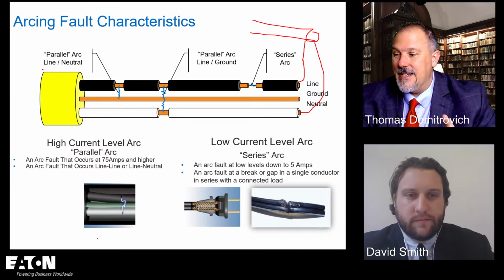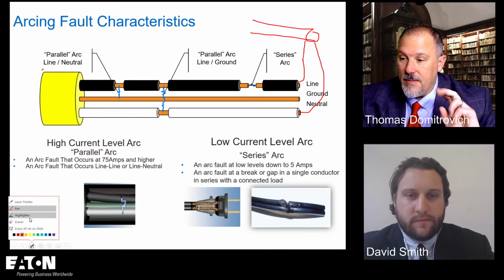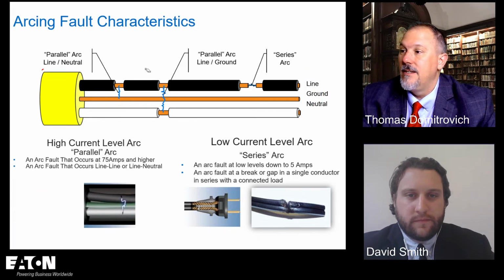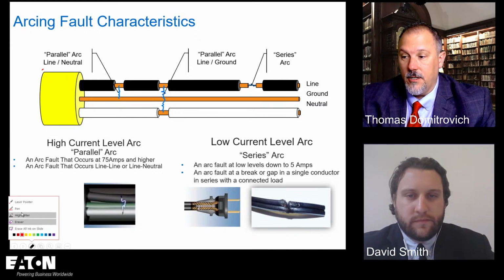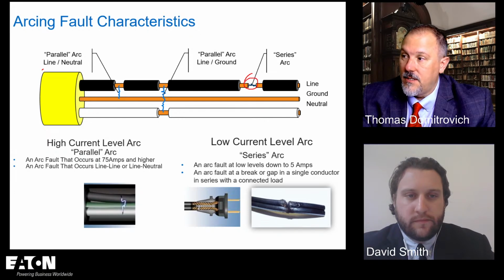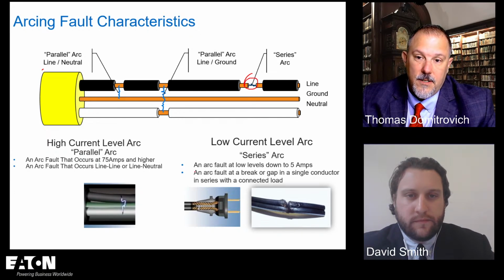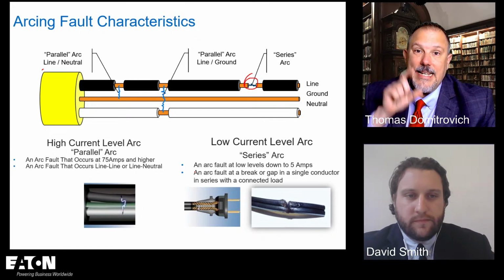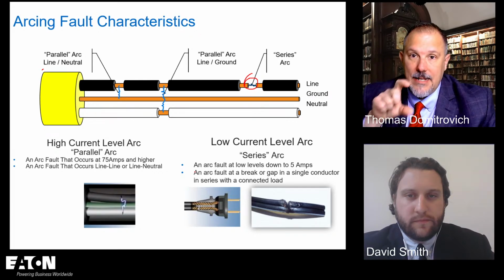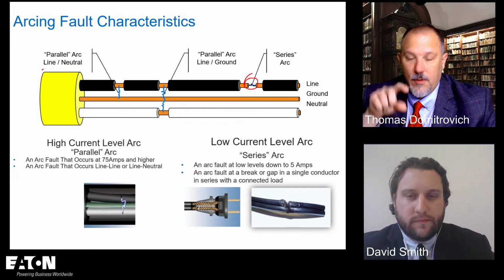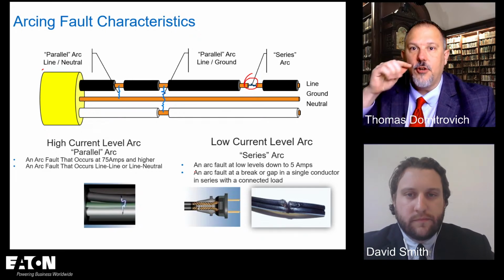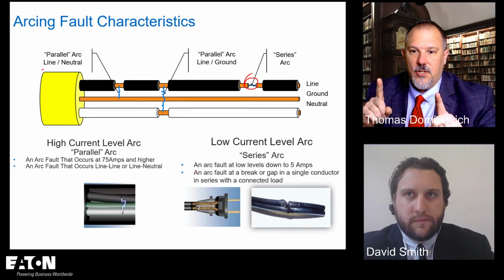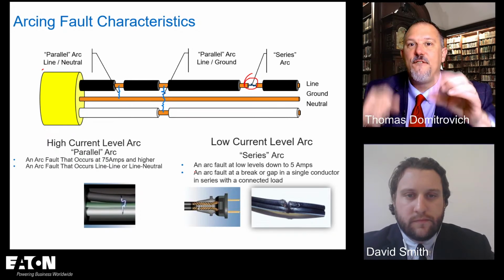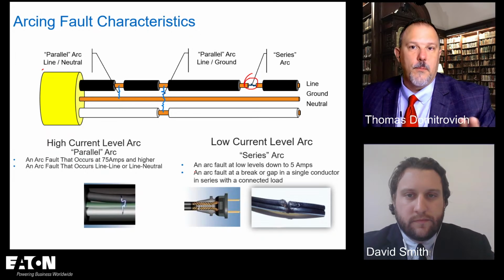But in 1699 for the branch feeder, before the combination type device, we also tested for a low 5 amp arc in series with that conductor. So a branch feeder AFCI device can detect line to line arcing, line to neutral arcing, line to ground arcing, line to a pipe arcing, and also series arcing at 5 amps. Everything else is done at a 75 amp trigger point.